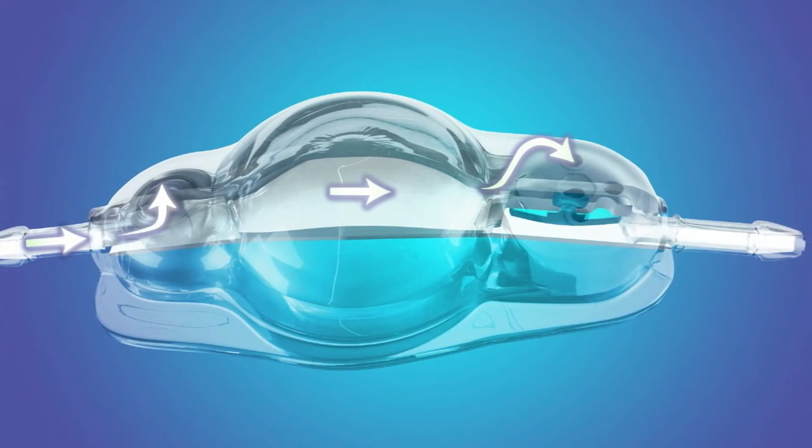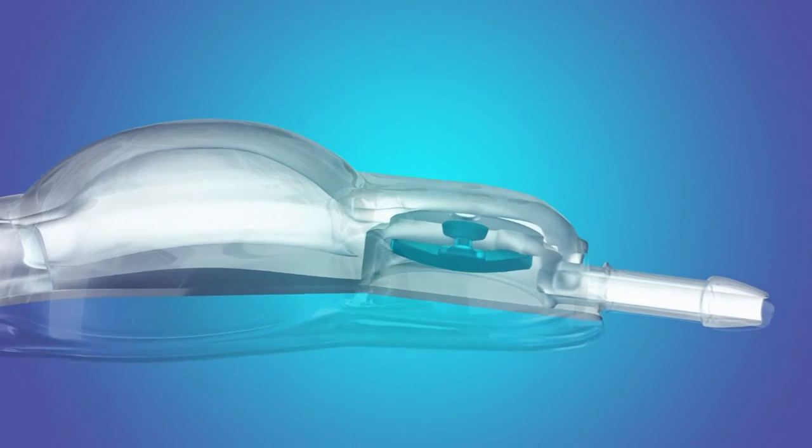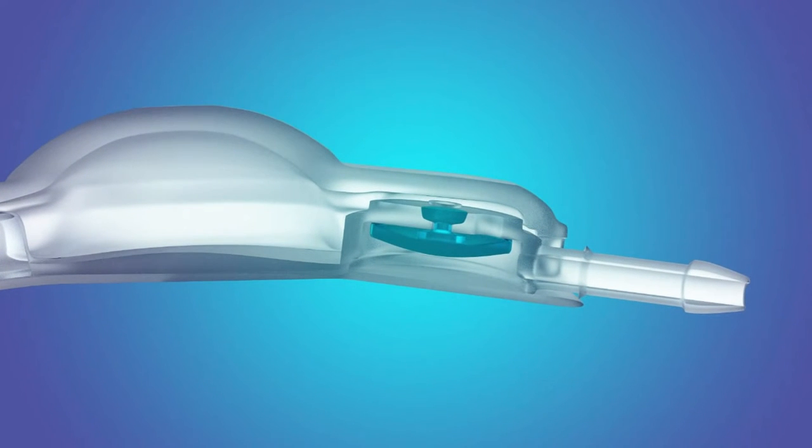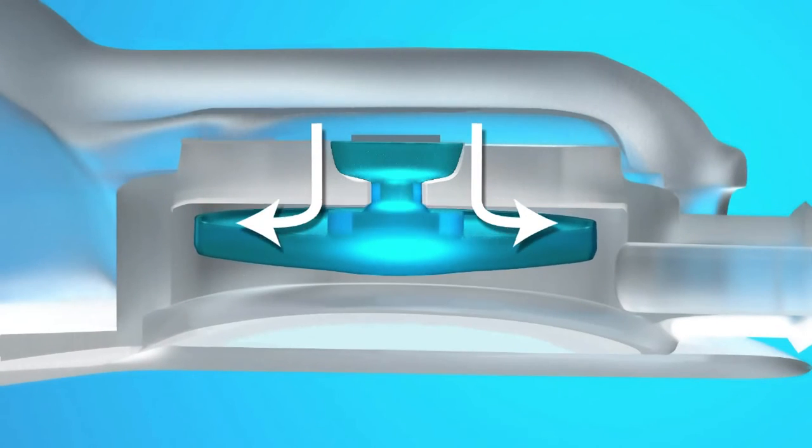From the reservoir, CSF flows through the valve mechanism flow holes. The inlet CSF fluid pressure causes the umbrella-shaped membrane to open when intracranial pressure ICP exceeds the resistance of the valve umbrella or membrane.